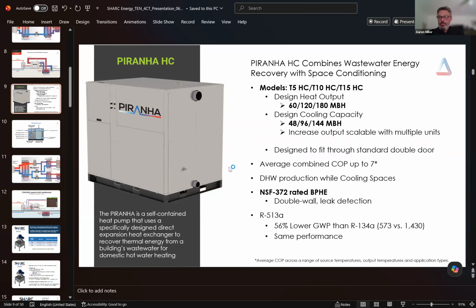So I kind of blew through this because I didn't want to just sit here and read to you, but we use an NSF 372 rated brazed plate heat exchanger. What that means is, again, the sanitary stays completely separated from the refrigerant, and the refrigerant and the sanitary both stay completely separated from the potable hot water. And if there is any leak, it'll all go to environment. There will never be any cross contamination.